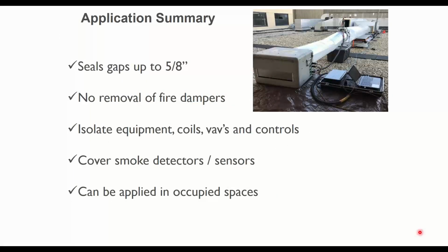As mentioned, up to a 5/8 inch gap can be sealed. You do not have to take out dampers. You can either seal through the dampers, which at my own personal house, I did this 9 years ago. Right when I started getting ready to teach classes on it, I'm like, I got to see how it works. We were going to do it at my coworker's house, but then his wife said, no, nobody can come hang out at our house for the day. So we did it at my house. My wife was also not happy, but we did it anyway. But in any case, I have a zone damper system at home, and I just drove all my dampers wide open, and we just sealed right through those things.